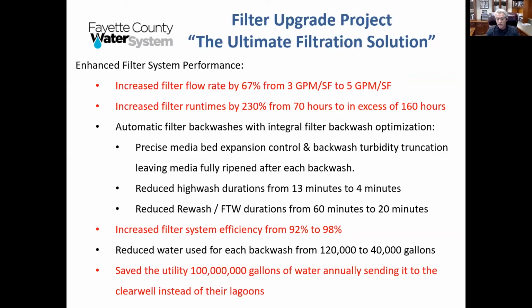And that's a filter to waste, it's sometimes also called. And they were having to rewash or re-season their media after every backwash because of the overwashes for over an hour, over 60 minutes. And today, because they're not overwashing the media when they do a backwash, that number's down to 20 minutes. All of this water savings that took place by perfecting their backwashes increased their filter system efficiency from 92%, which is very low, to 98%, which is way above norm. Norm is about 97%. And the definition of this efficiency is filters backwashing time versus run time, and that's how they determine that number.